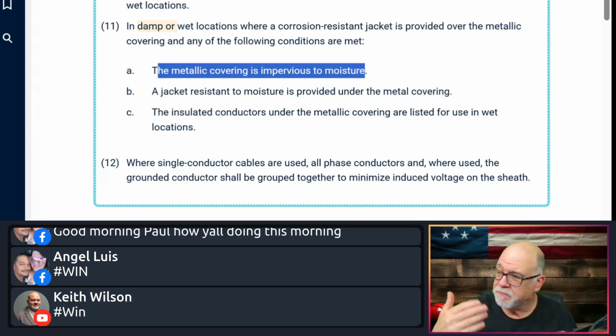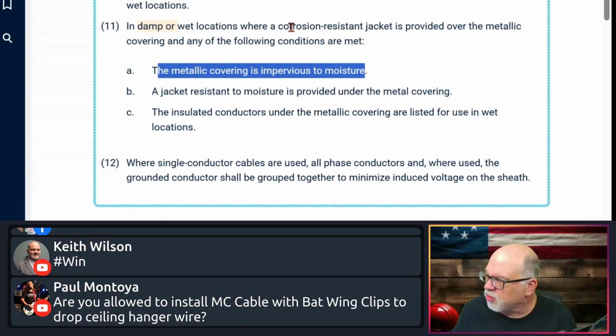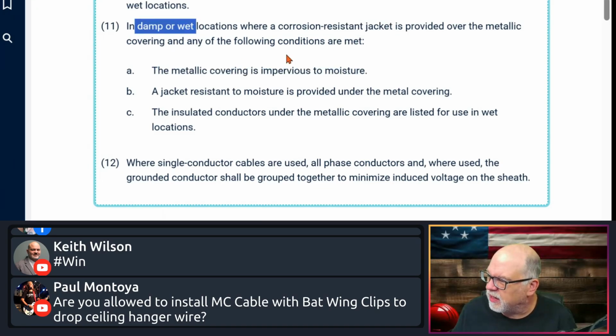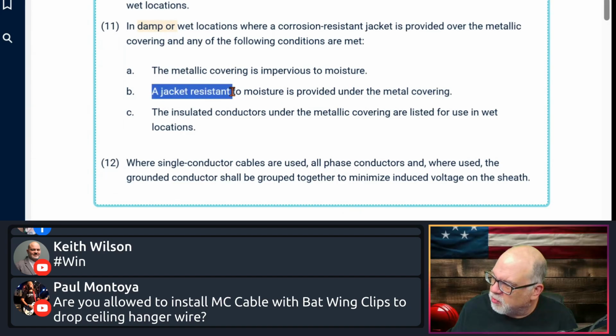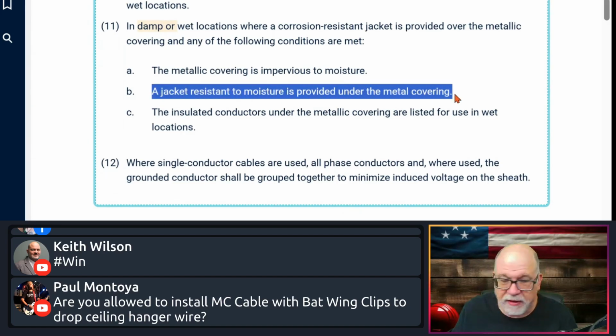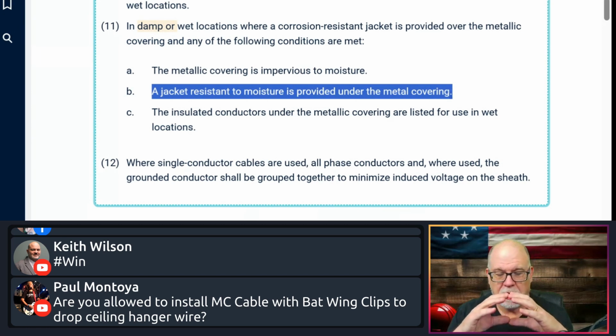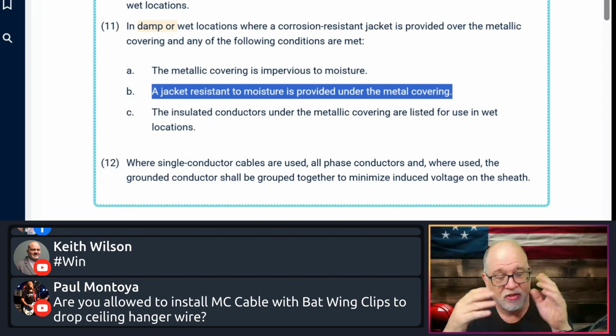It's also a smooth one, and this also qualifies as an equipment grounding conductor, believe it or not. So again, that's an example of a metallic covering that is impervious to moisture. You still have to have this corrosion resistant jacket if you want to use it in these locations. Or it could have a jacket resistant to moisture provided under the metallic covering. So you could have an outside metal MC, and then underneath it, you could have a jacket as well. That means the outer protective covering is on it, and then you would have an interior jacket resistant to moisture provided under the metal. That would typically be a binder, let's say, that wraps around the internal conductors. It would have to be, in that case, resistant to moisture.